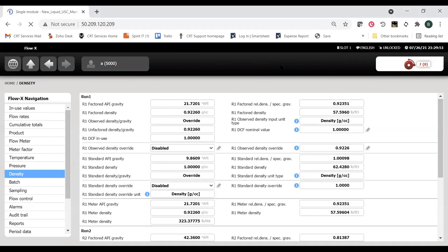As Henry was talking about density, one of the things I wanted to point out is that with density, as we measure the density, we can use online densitometers, and some meters have a characteristic of also being able to measure the density. What I'm showing here, and I believe David had shown this earlier last week, is a flow computer. Now, the calculations that Henry has been doing manually are all algorithms that are typically built in to flow computers.